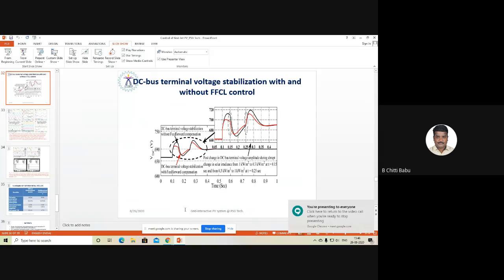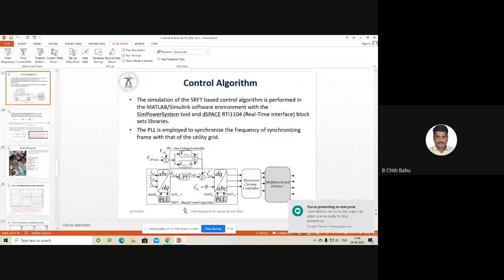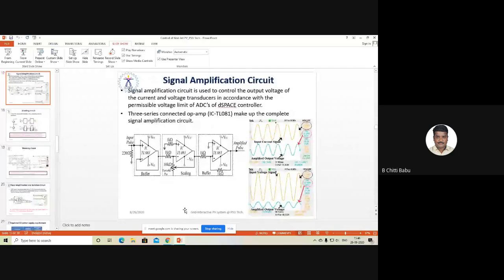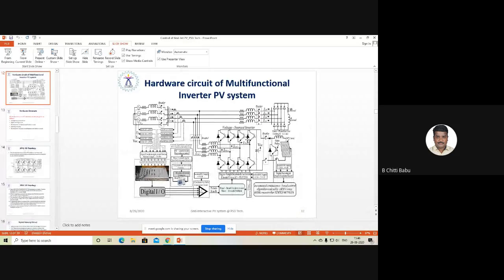Let me show you the figure here. Without the fourth leg, neutral current flows between the neutral terminal of the supply and the neutral terminal of the load. So there is a strong injection of neutral current between these two. The third harmonic current is circulating, so your neutral wire is overheated. Now you have a fourth leg, so the third harmonic current or neutral current is bypassed towards this terminal instead of going towards that terminal. It provides an alternate path for neutral current, so the third harmonic is compensated and the supply current remains sinusoidal without any third harmonic. That is the concept.